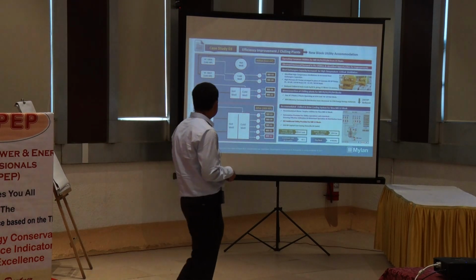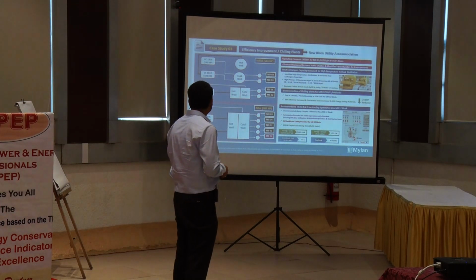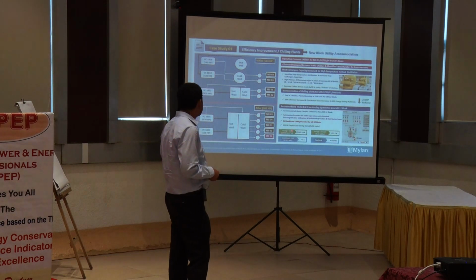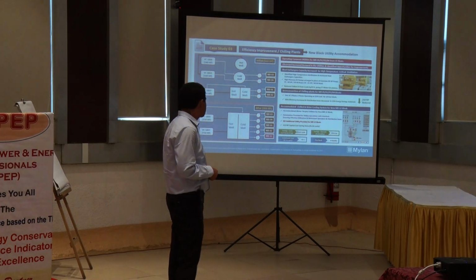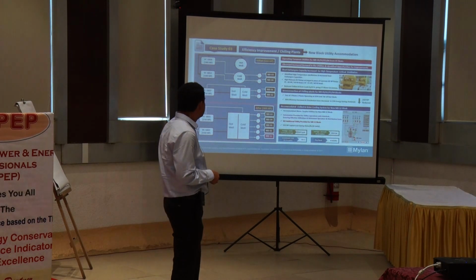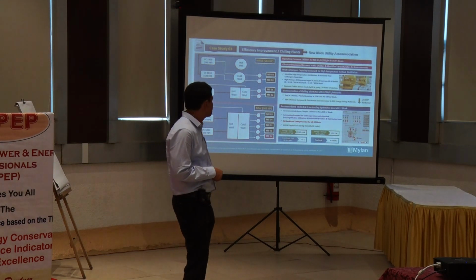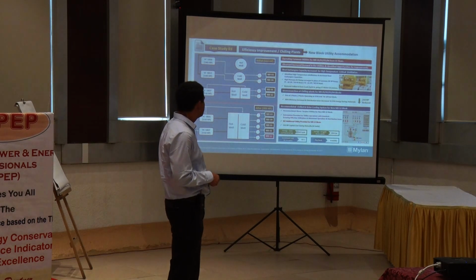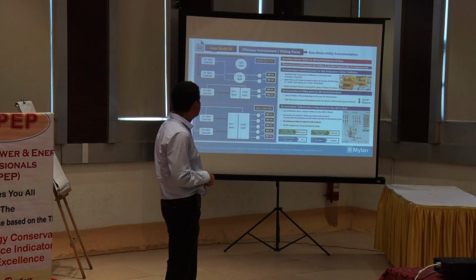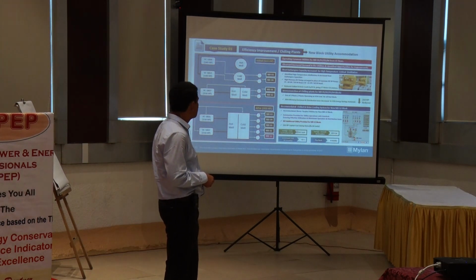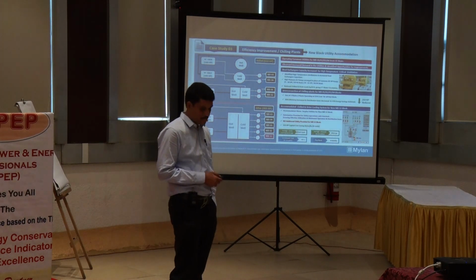With those modifications, we have disconnected one chilling plant from the circuit, and we have added one more production block to the existing circuit. With this, we are able to reduce 210 HP. We have disconnected from the circuit one chilling plant, and we have avoided 550 HP capital cost of new block utilities. This has given a huge saving, 424 lakhs for 4 years, and investment is very less, 65 lakhs, and payback is 8 months.